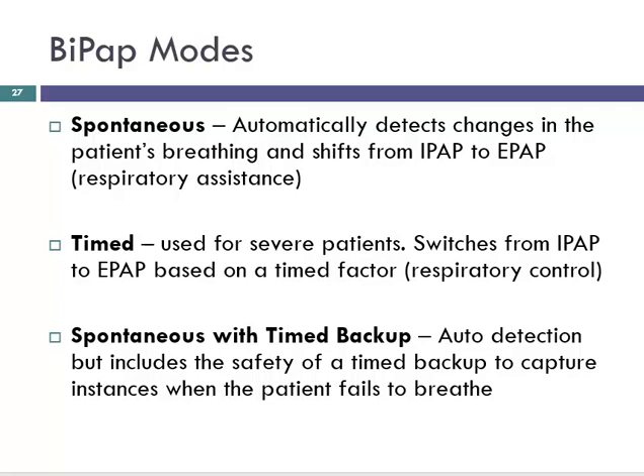Spontaneous mode is the mode that we use most often, which means the patient is initiating the machine to alternate between IPAP and EPAP. It's just going off of their breathing pattern. We can do timed mode, which is almost like a ventilation device where the machine automatically switches between inspiration and expiration and breathes for the patient. They can't initiate their own breath. They have to breathe with the machine. Pretty uncomfortable, so it's really only used in really severe cases. What's used more often is spontaneous with a timed backup, which means the patient can initiate the machine alternating between inhalation and exhalation. But in an instance like central sleep apnea, where they fail to initiate a breath, the machine will kick on, initiate the next breath, and automatically start delivering the IPAP to make them keep breathing.